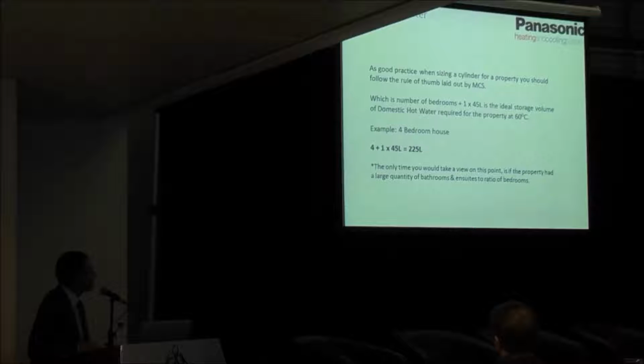Hot water requirements. Normally we're talking about 50 litres hot water a person a day, unless you have teenage daughters, where it can be considerably greater. So generally when we're looking to size the cylinder, we take the number of bedrooms, add one and multiply by 45 litres, because of course our heat pump is heating not just the rads, but also the hot water.